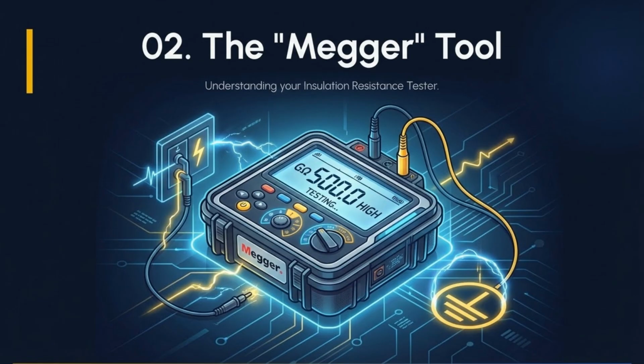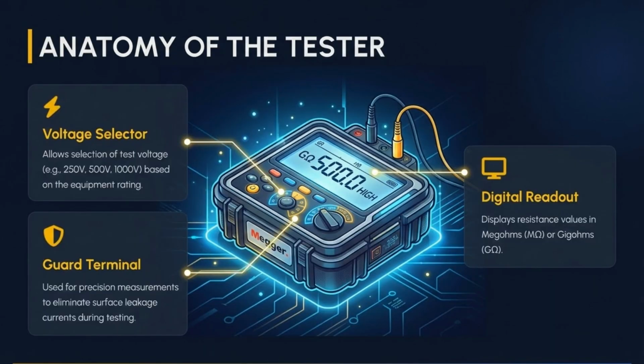Next, we'll focus on the essential tool for this test, the Megger, which is your insulation resistance tester. Understanding this device is key to accurate testing. The tester includes a voltage selector for choosing the appropriate test voltage. The digital readout displays resistance in megohms or gigohms. A guard terminal is also used for precision, helping eliminate surface leakage currents.